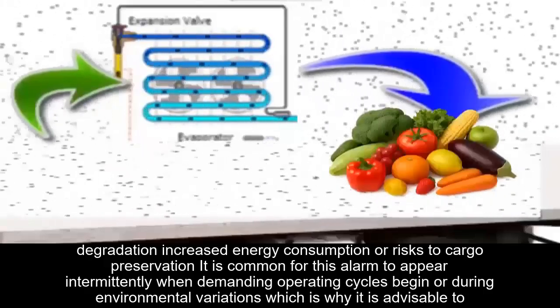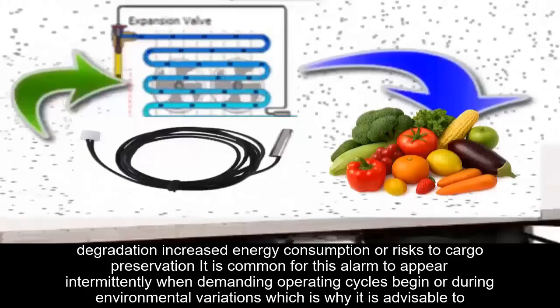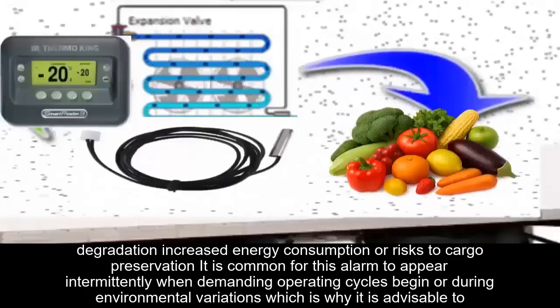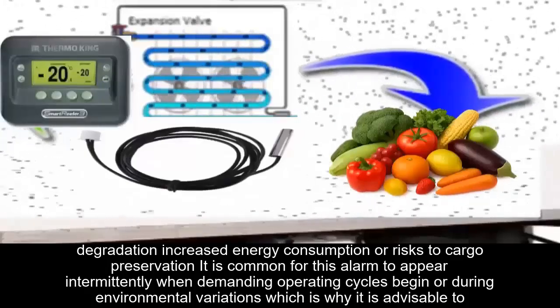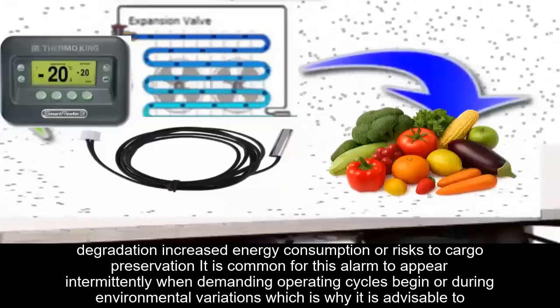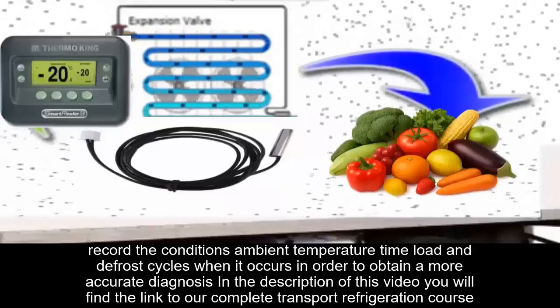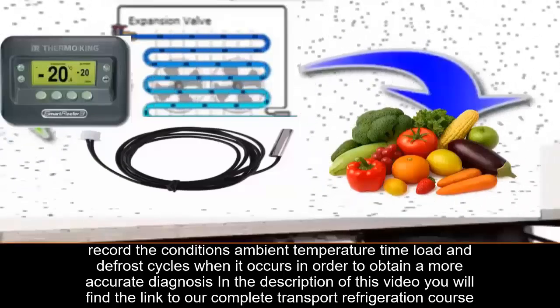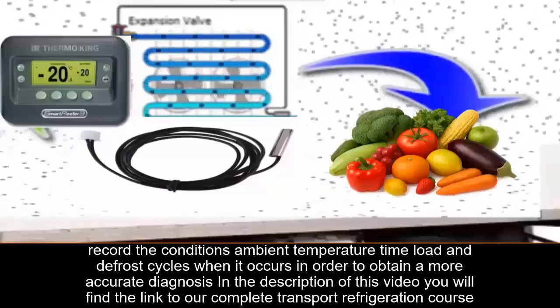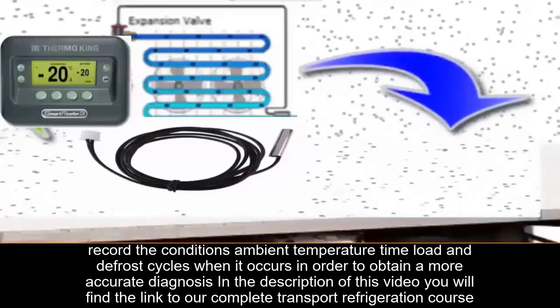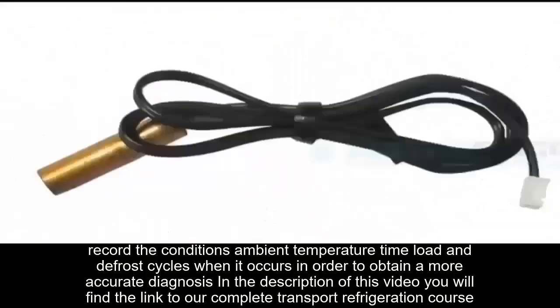It is common for this alarm to appear intermittently when demanding operating cycles begin or during environmental variations, which is why it is advisable to record the conditions, ambient temperature, time, load, and defrost cycles when it occurs in order to obtain a more accurate diagnosis.